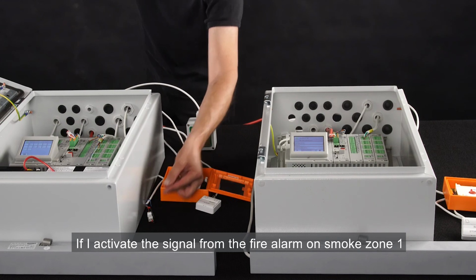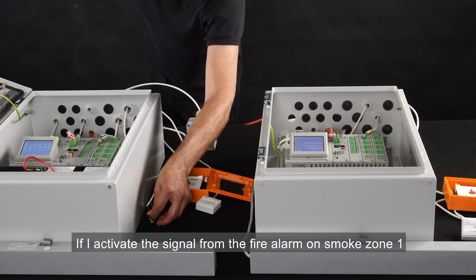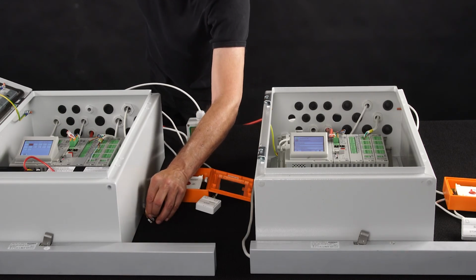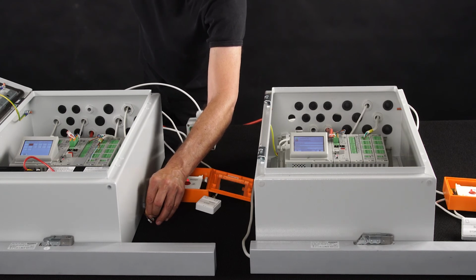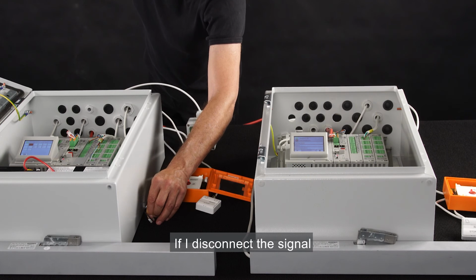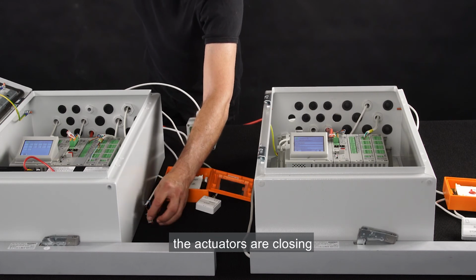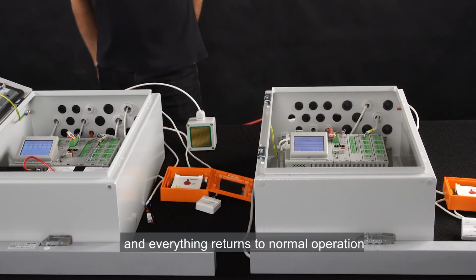If I activate the signal from the fire alarm on Smoke Zone 1, the 2 zones are reacting. If I disconnect the signal, the actuators are closing, and everything returns to normal operation.